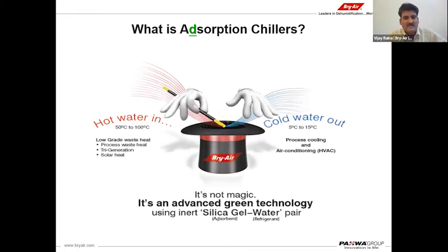What is an adsorption chiller? It is nothing but we use hot water as an inlet and we generate chilled water within some temperature range. Minimum is 5 degrees and maximum can go up to 20 degrees centigrade by using hot water, which is a low grade waste heat available from any industry. It's not magic, it is an advanced green technology. We use silica gel as an adsorbent and water as a natural refrigerant in this technology.